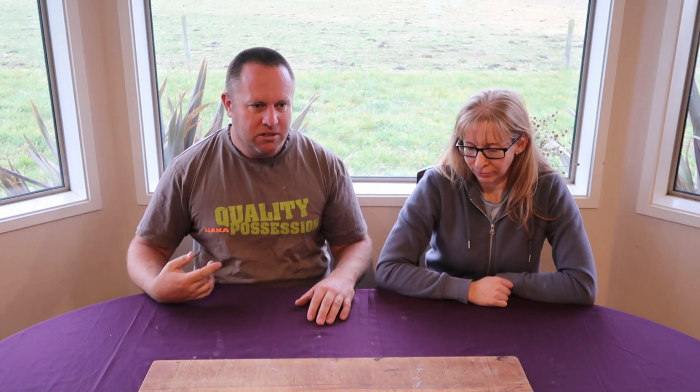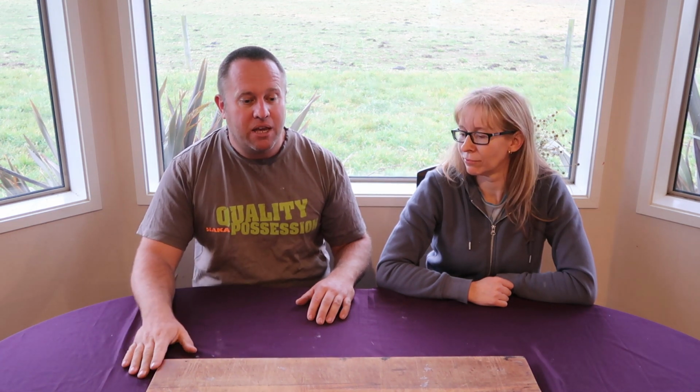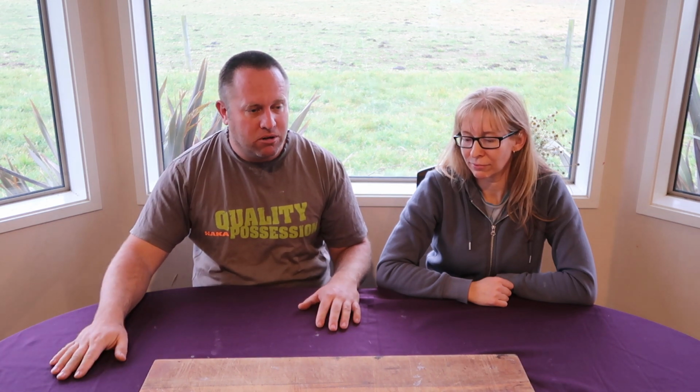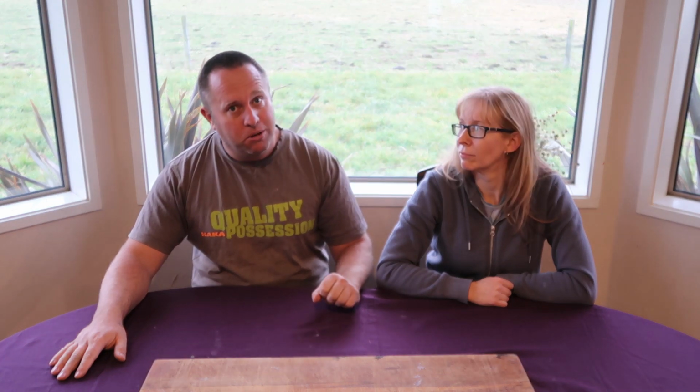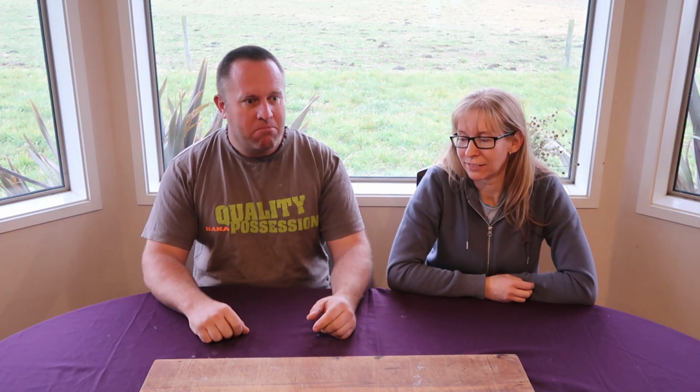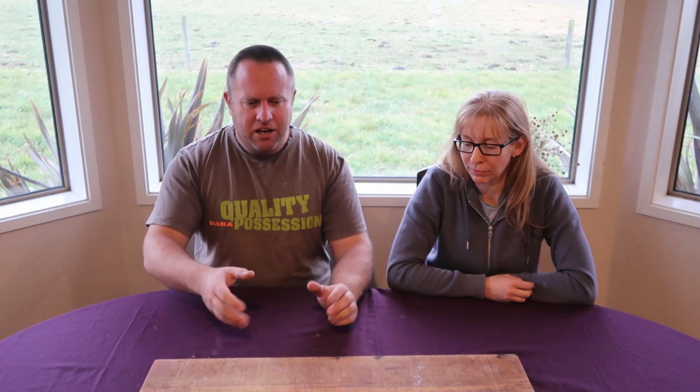So I was going to put a duct vent into each room, but because the doors open into the rooms, if the fan pressure is too great, and I have had this happen, someone hit up the builders and they didn't know what was going wrong. They'd leave the fans running overnight, and this old lady got up out of bed in the morning and she couldn't open the door. It was only a 150mm duct with a supply in 2 rooms, and she had a heat pump running, or I think it might have actually been an LPG fire. So anyway, she had it running and she couldn't open the door.